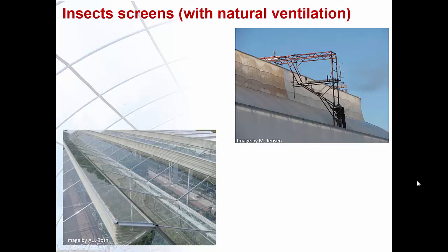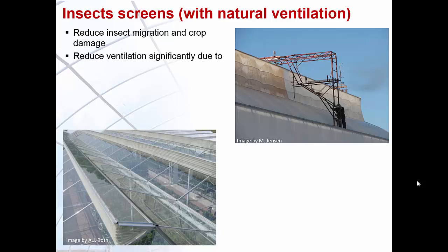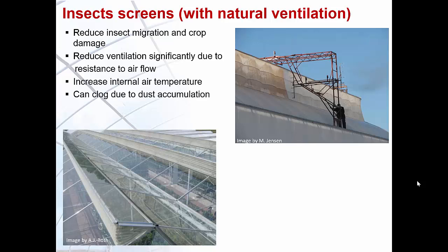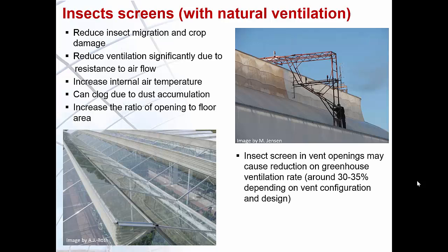Insect screens are commonly used with naturally ventilated greenhouses. They help reduce insect migration and crop damage. However, insect screens can significantly reduce ventilation due to resistance to airflow and also increase internal air temperatures. They can clog due to dust accumulation. Research shows that insect screens in vent openings may cause a reduction in greenhouse ventilation rate of about 30 to 35 percent, depending on ventilation configuration and design. Combined use of roof and side vents is recommended when using insect screens.